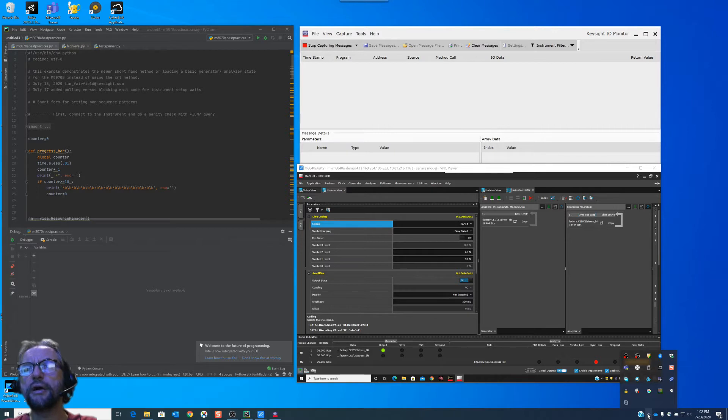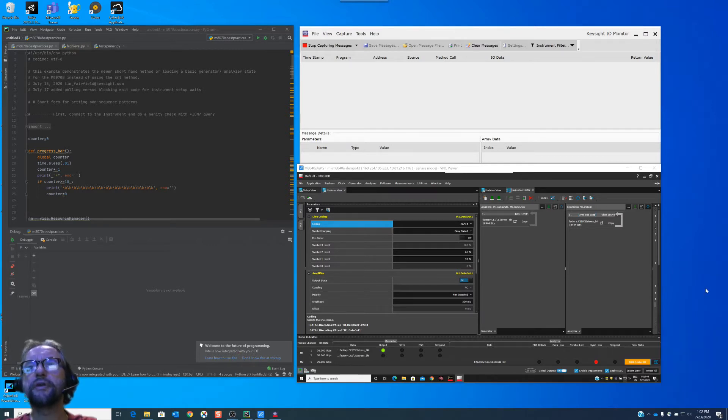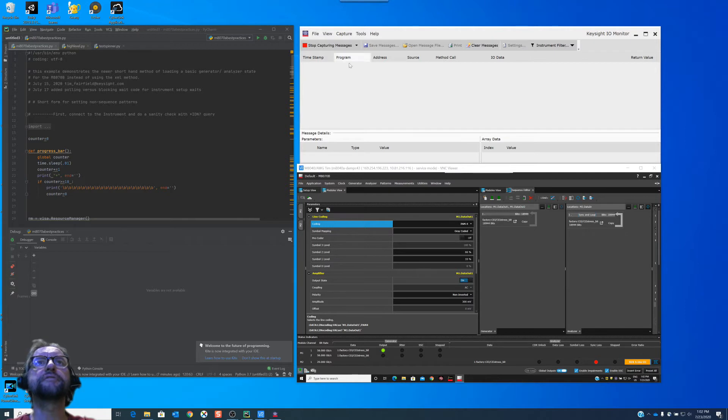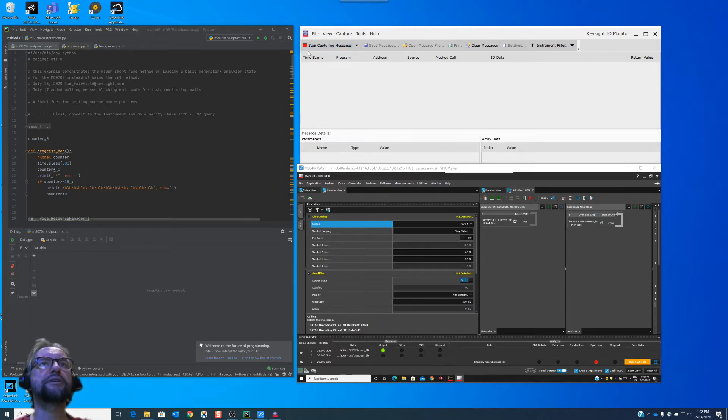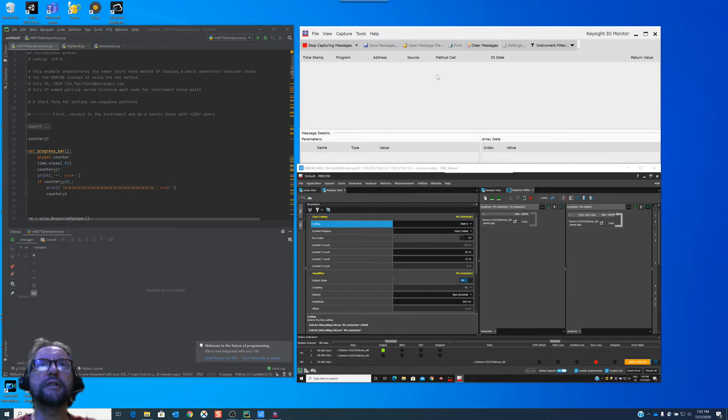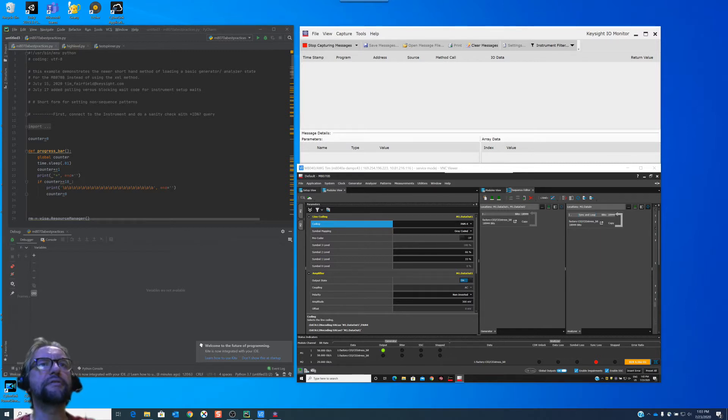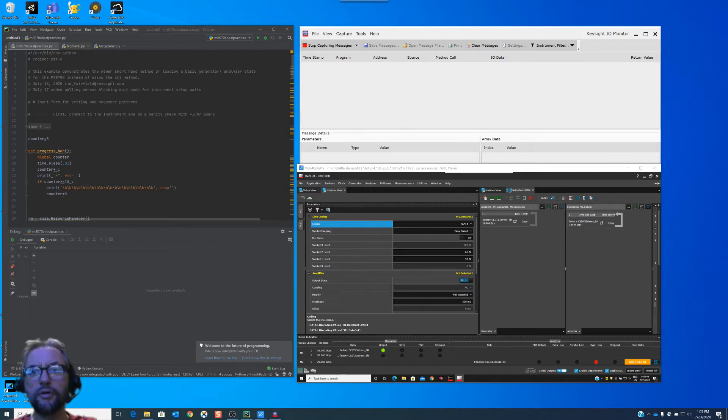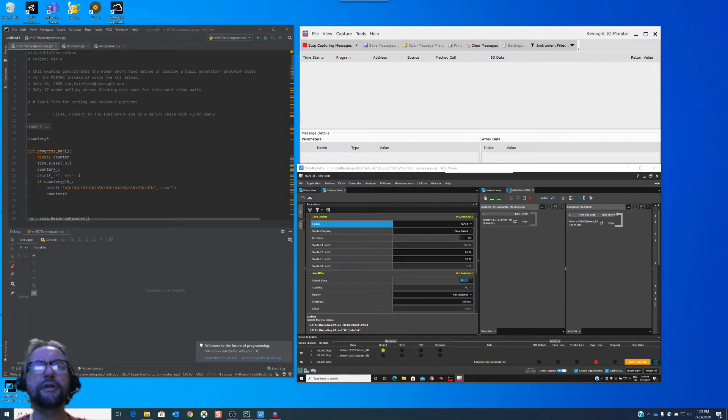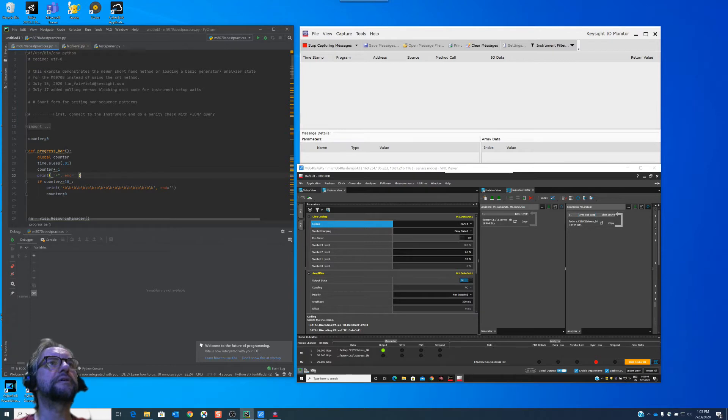If you're running IOLibs, IOLibraries here, Utilities, IOMonitor. That's where I'm getting that from. So this will open it up. You can start capturing messages. And when we start executing code, the messages that go across the Visa bus, the virtual bus, it will basically be listed here. And it will have timestamps and things like that. So it is useful. So we are automating this software with this Python code. This is running on a, I'm on a remote location and my instruments are in another room. And this is a VNC window. So I'm remoting into that as well. So let's get started.